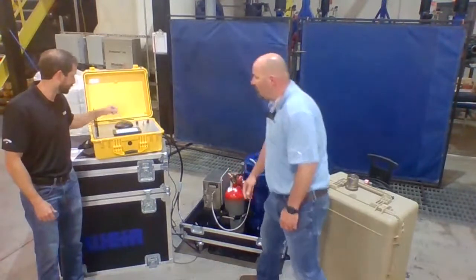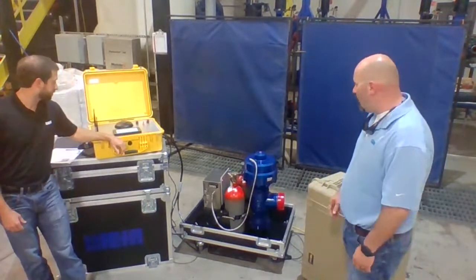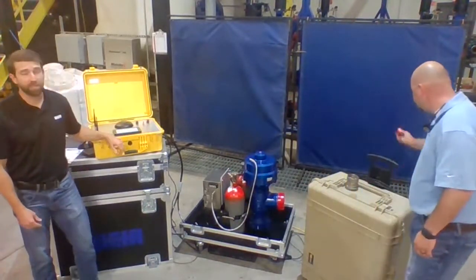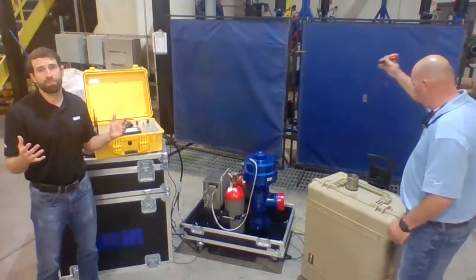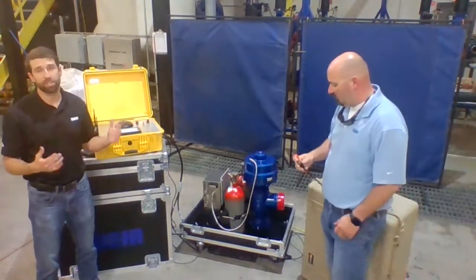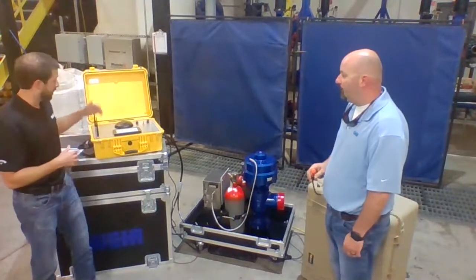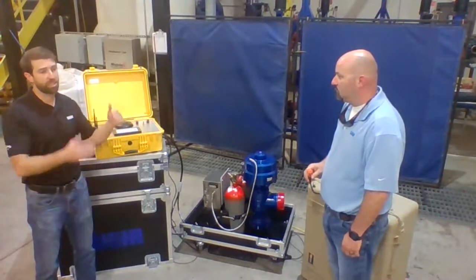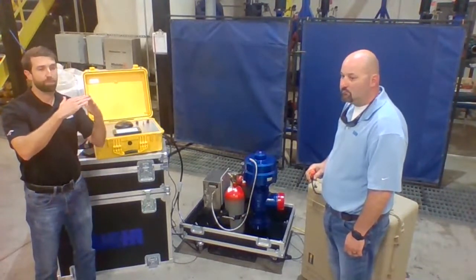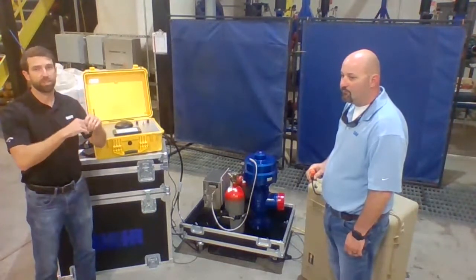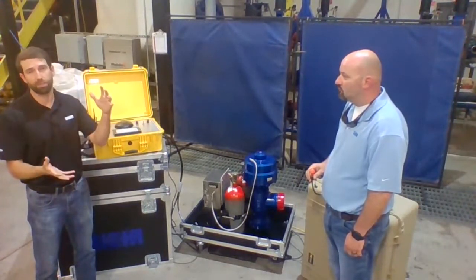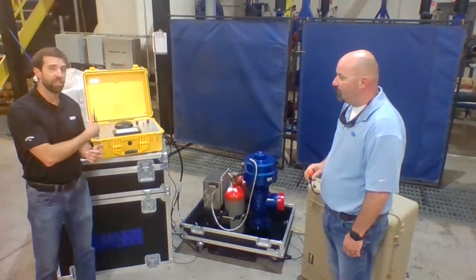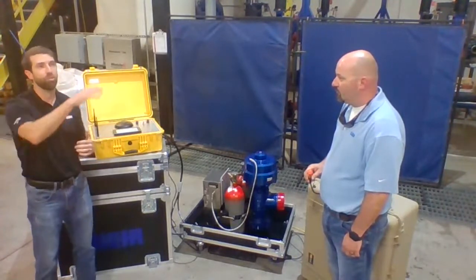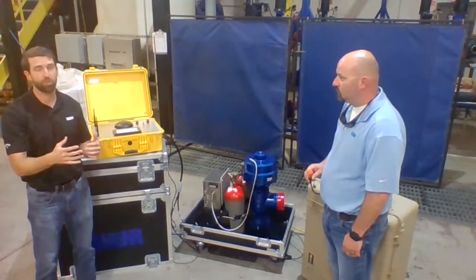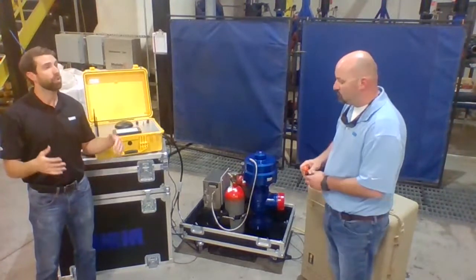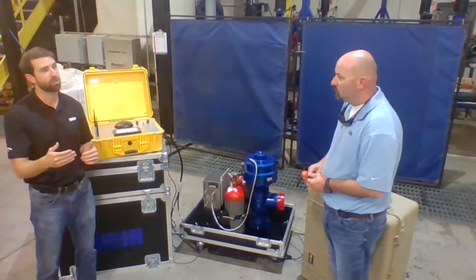What does the system say—are we armed and ready to go? At this point, from a customer standpoint, once you've got your nitrogen and everything hooked up, the only thing you have to do is enter your pop-off pressure. This is the value above which the system will dump the nitrogen and completely open your valve. The other value you enter is the reset pressure—what you want the pressure to drop back down to before you feel safe closing the system back up and getting right back to working.